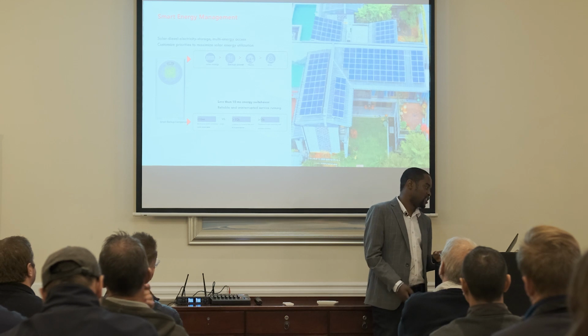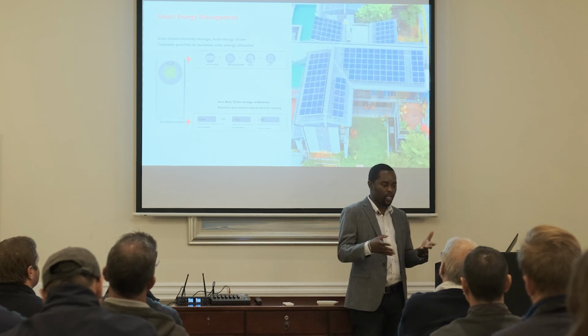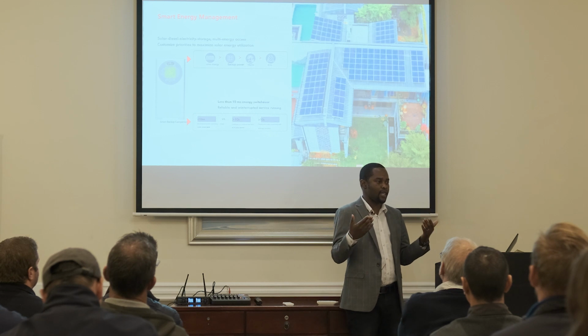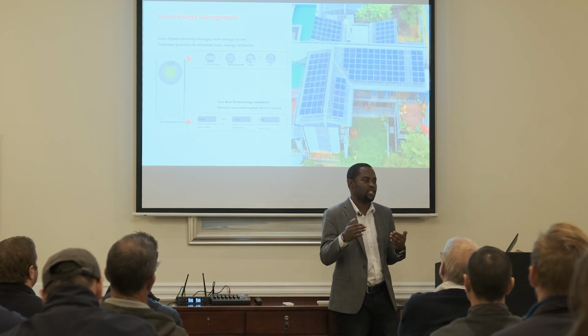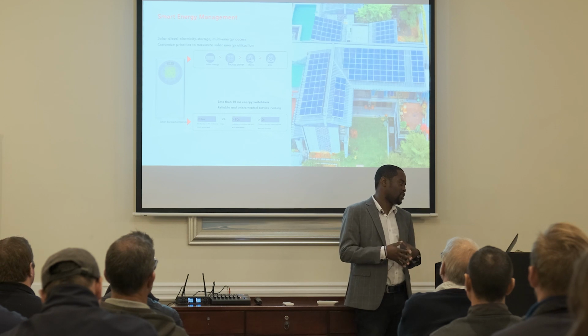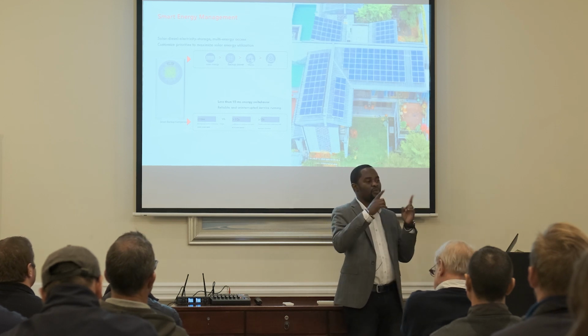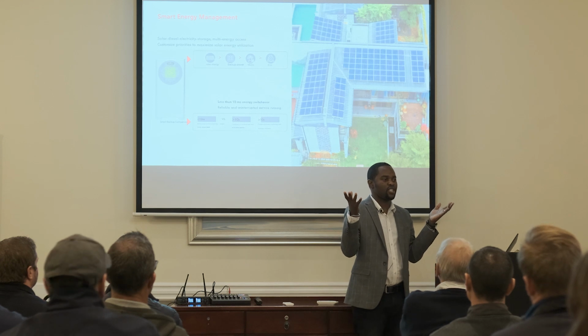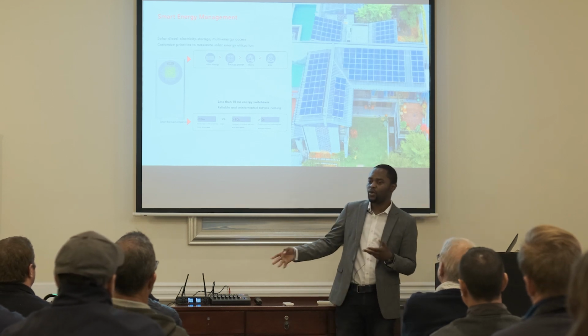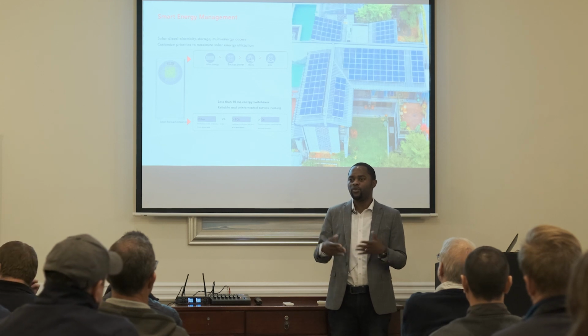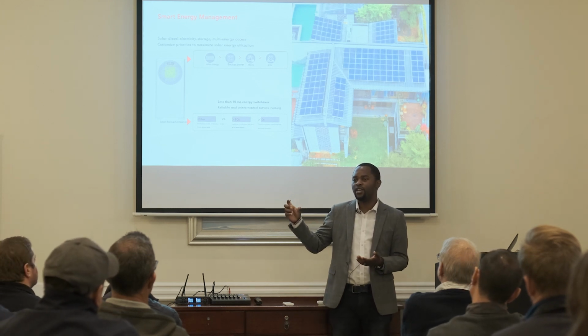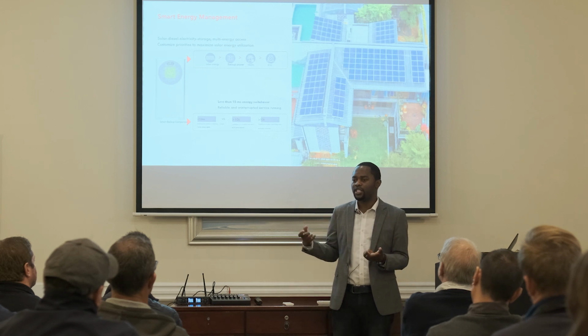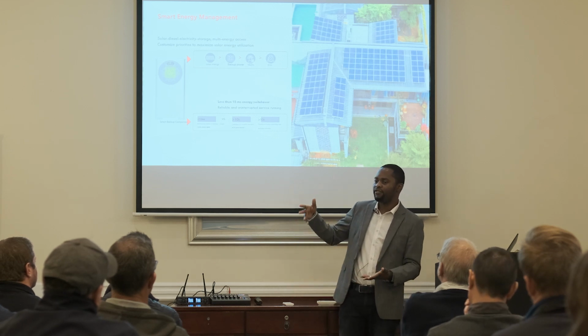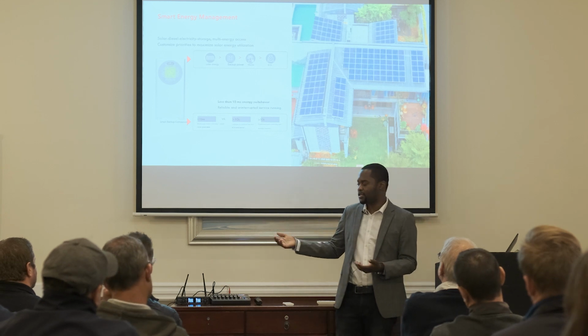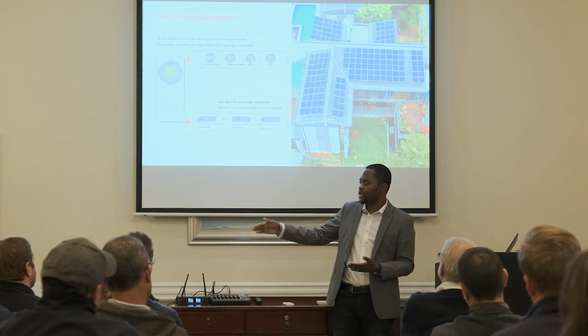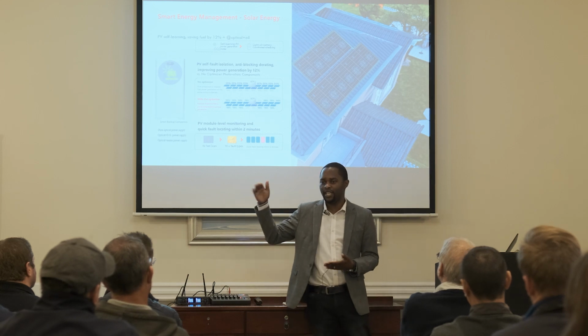Then when that is not enough, you also want to look at your battery. Am I lower or higher than my reserve SOC? Right? If your SOC is greater than your reserve SOC, then that power is actually useless power because you are not using it. For instance, you've got 3 batteries and you know during load shedding in your area, it can only be up to 2 or 4 hours. Then with 10 kilowatt hour, you can actually withstand the worst load shedding in your area. So what it means now is 10 of 15, which is around 66%. Then you can actually go to the inverter, which sets 60% as your reserve SOC.